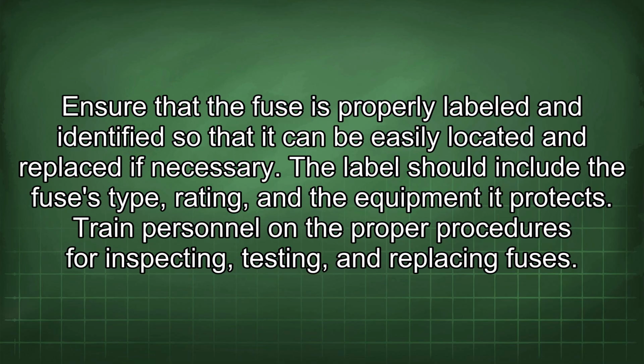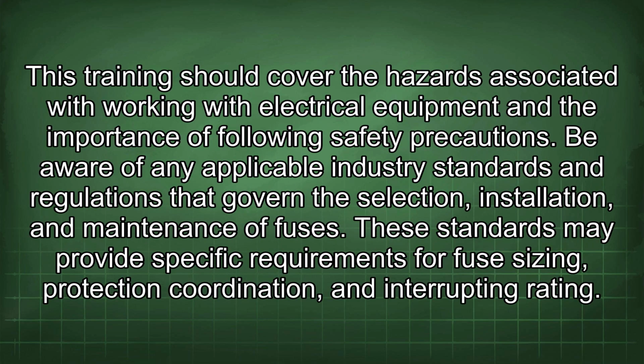Ensure that the fuse is properly labeled and identified so that it can be easily located and replaced if necessary. The label should include the fuse's type, rating, and the equipment it protects. Train personnel on the proper procedures for inspecting, testing, and replacing fuses. This training should cover the hazards associated with working with electrical equipment and the importance of following safety precautions.